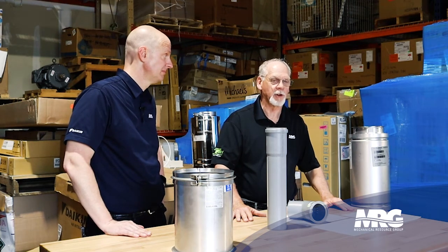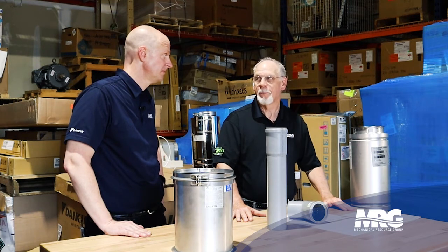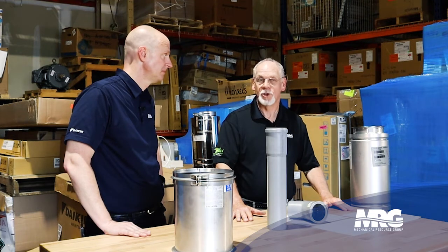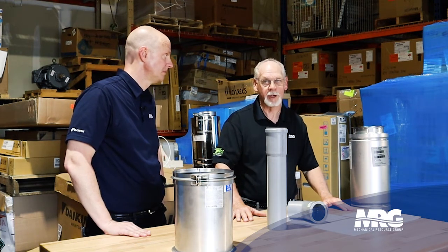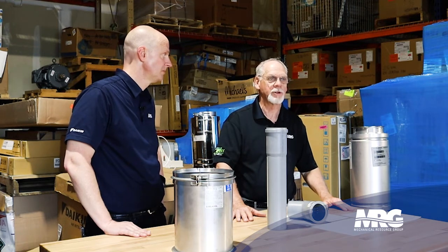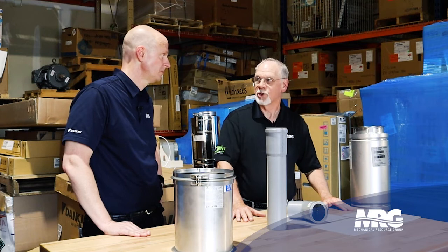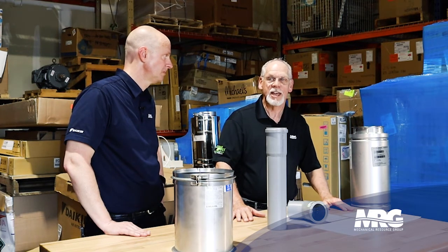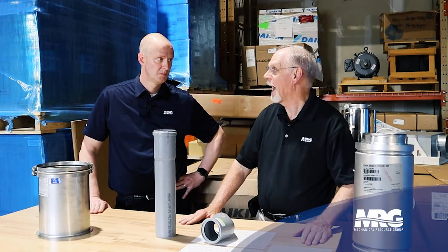The other thing that's another critical thing is you've got to have some barometric dampers so that when something is not running, you don't have the flue gas going in the wrong direction. It's got to be going out. So you have some barometric and backdraft dampers in your system so that it can draw like it should, because that's the natural way for it to vent, is that as it heats up and that air expands, it's going to rise.